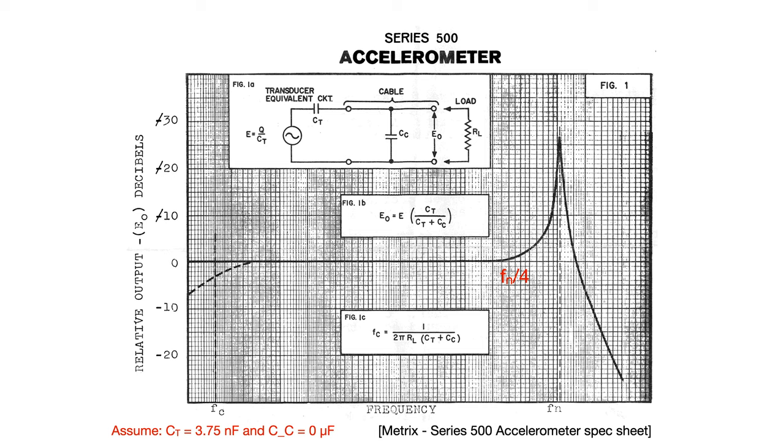This is a sketch of the frequency response plot for the accelerometers we will use in the lab. In the middle range of frequencies, you can see that the plot is flat. This is where we would like to use the accelerometer most, in this range of frequencies. Because in this range of frequencies, the acceleration will be proportional to the voltage output of the accelerometer.